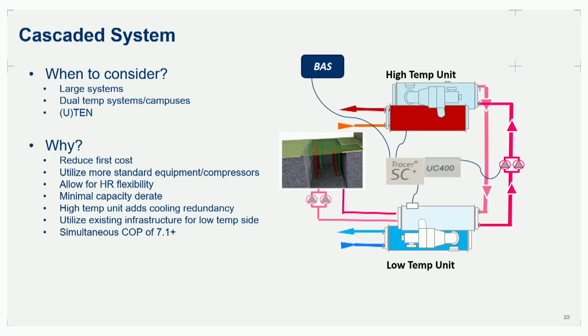Also, by splitting this up, we give you access to this kind of intermediate loop. We call it the energy transfer loop, and that's the loop that goes from the condenser of the low temp machine into the evaporator of the high temp machine. And that's typically a lukewarm loop, like 90, 100 degrees, somewhere in there. But this allows you to do a lot of heat recovery. So if you have any other heat sources besides your primary, we can tie right into this loop and feed all that to your high temp machine. This could be geothermal, this could be wastewater heat recovery, it could be cooling loads in the space. There's really a lot of options, and it offers a lot of flexibility.